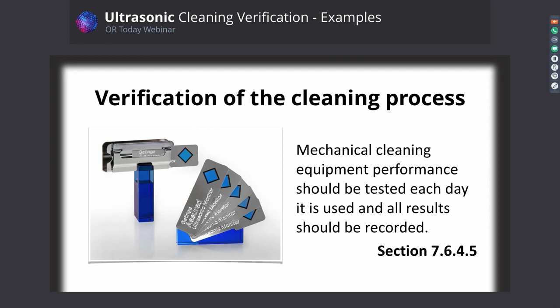Here's an example of where different levels of blue have been removed, different levels of soil have been removed, and if nothing's been removed, of course, it's a complete failure. But if there's any blue showing up, those also are considered a non-pass. If the blue is completely removed, that's considered a pass. And this one type of cleaning verification is easy for record keeping. It's really great for trend analysis because they're inexpensive and you can display several of these in a tray at one time at very little cost.